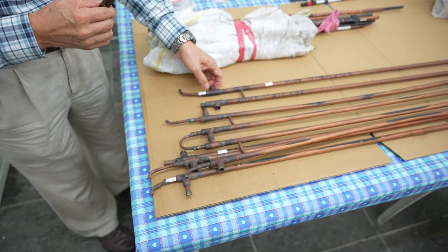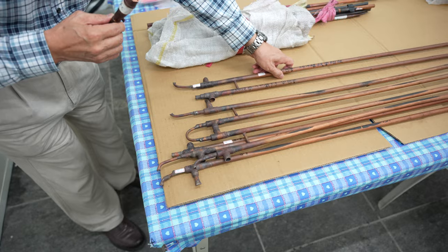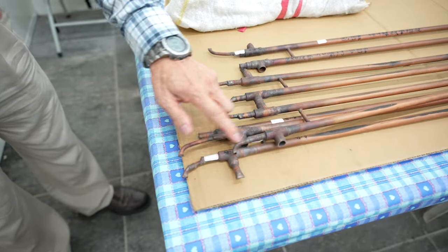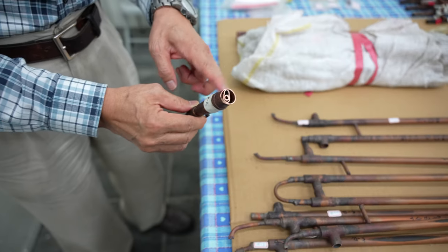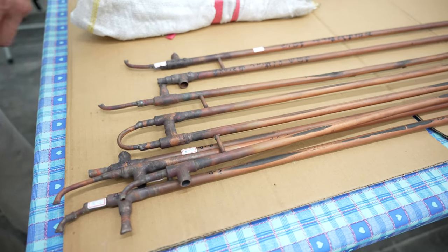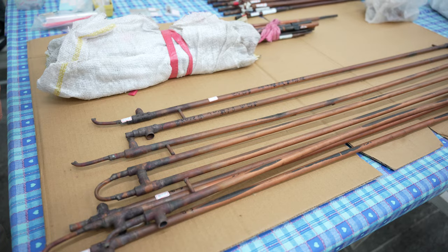What else have you got there? This is a very big heat exchanger, triple pipe. We just show you some of them. There's some damage here — like this, but in here. All have damage because of the flow capacity is blocked.